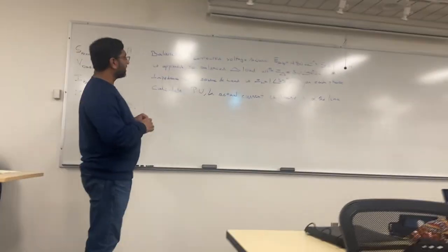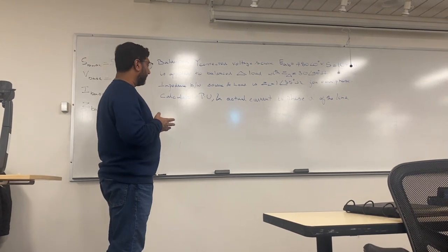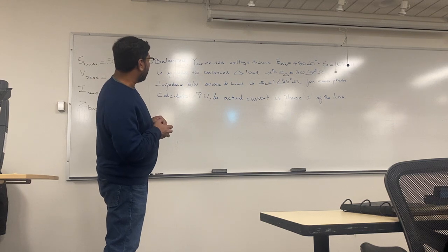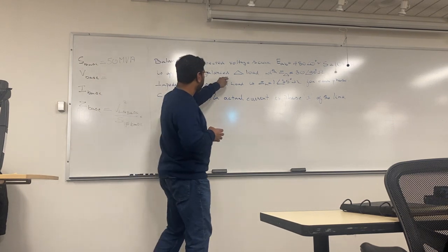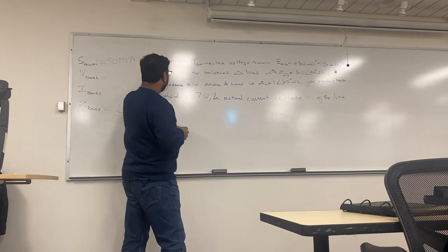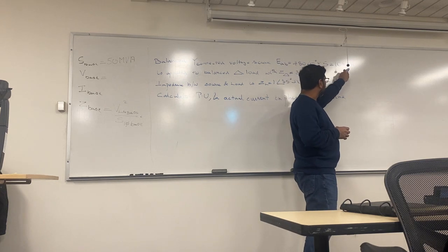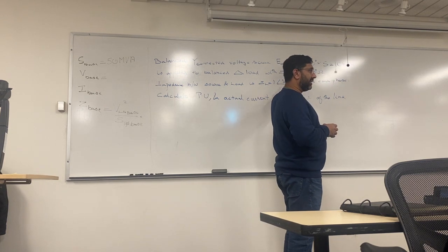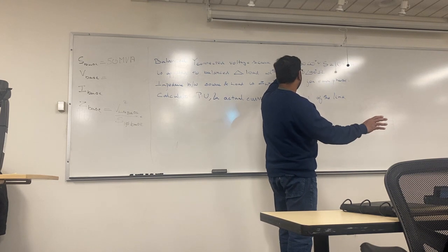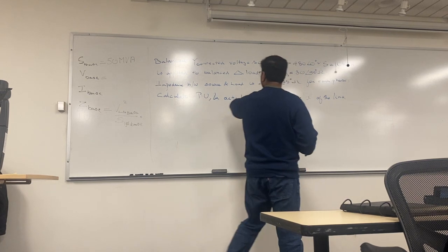I picked this problem because it brings into play your weeks 1 and 2. It does not bring power factors, I believe, because I did a balanced load, but it does bring a Y-connected source. So here's the thing. You have a balanced Y-connected voltage source with a certain voltage and a certain kVA. It goes without saying, this is the source, so pick this as your S base and V base. Right out of the gate, just pick your S base and V base.